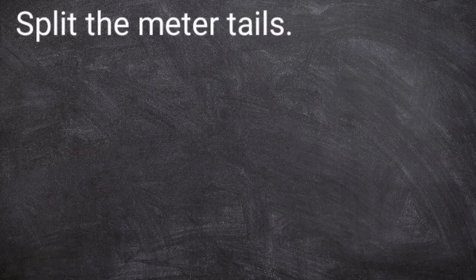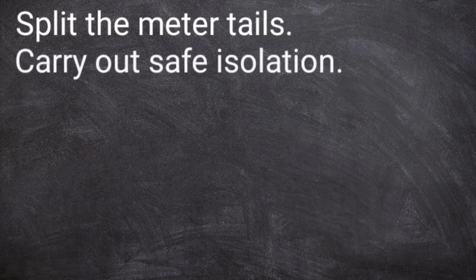So let's just summarise the video that we've seen here today, Gary. So we started off by looking at how to split the tails down and how essential it is that we get the right conductors into the right places in as safe a fashion as possible. So when we're talking about safety, primarily when it comes to this, Gary, what do we want to think about? We're talking about means of isolation. That may be local, so there may be, in our case, a switch to turn off the supply to the outgoing tails from the meter, or you may need to seek permission from the DNO to pull maybe the main cutout fuse, or to have a switch installed prior to connecting the new tails.